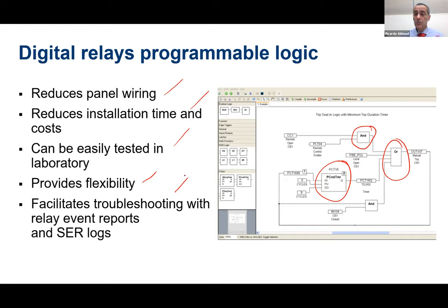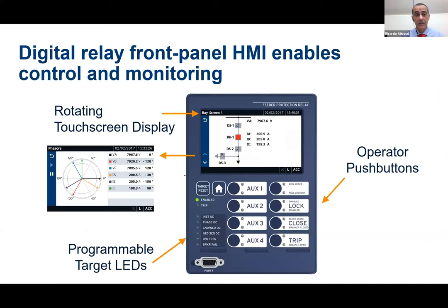And all of the variables that are part of this logic are included in the SER, that is the sequential event report, and also in the oscillography that is generated when you have any event. In terms of control and metering, the digital relays have the option for push buttons. So I can have dedicated push buttons on the front side of the relay, and I can configure those push buttons for different functions: open and close the breaker, open and close a disconnect switch, and so on.